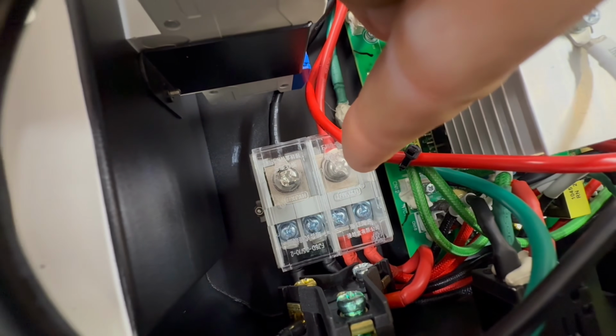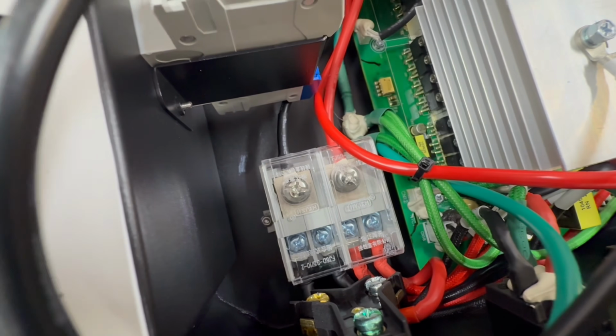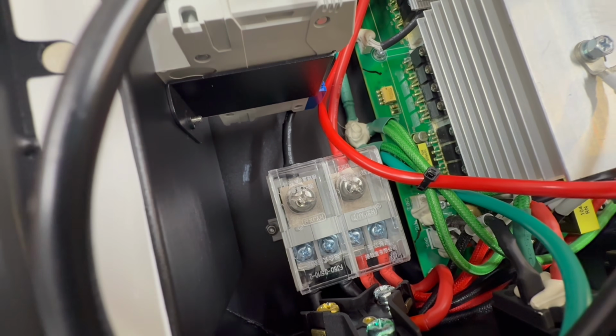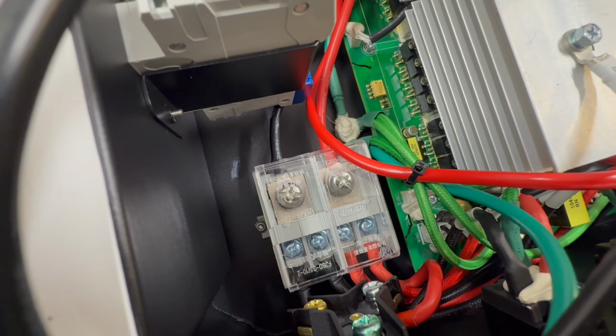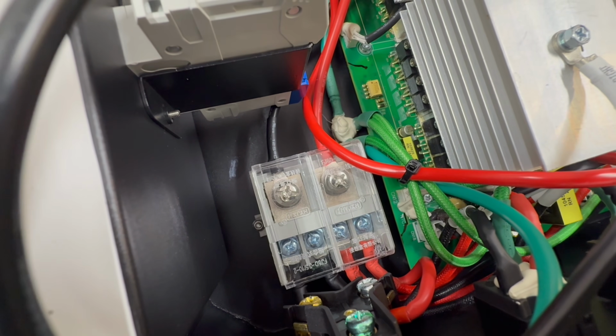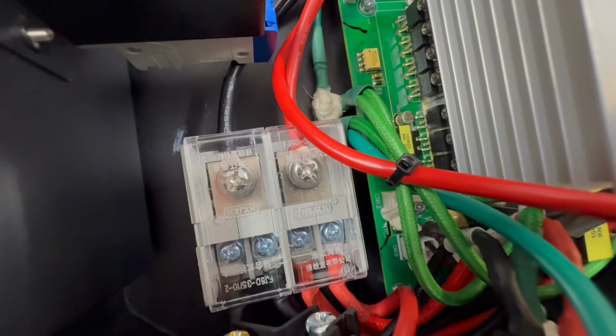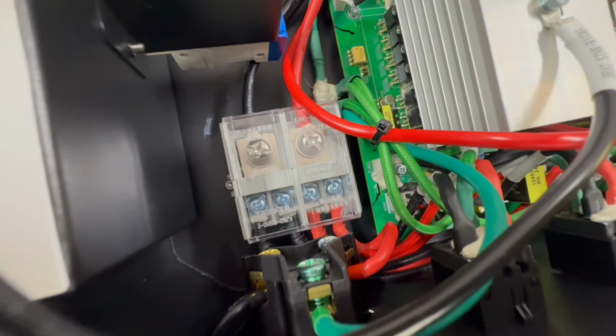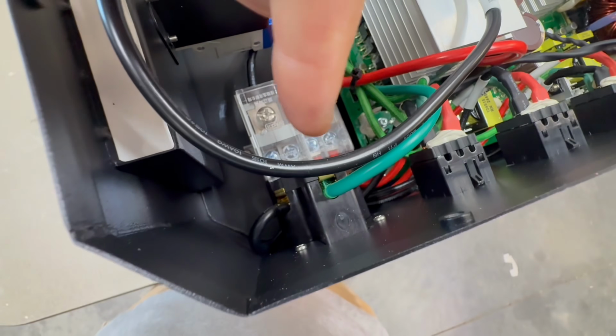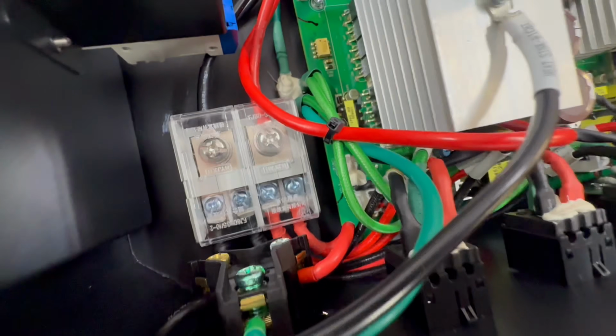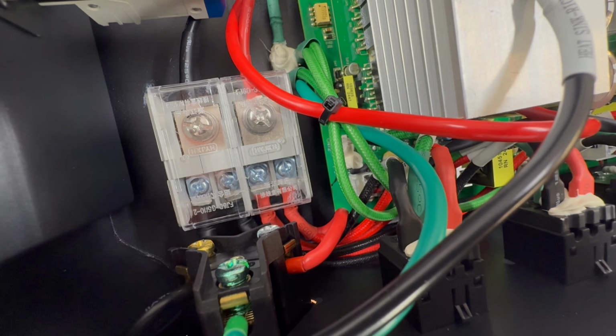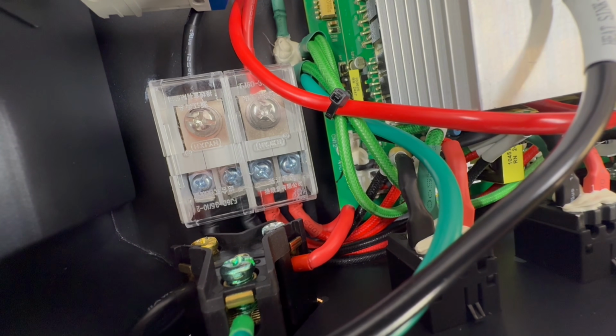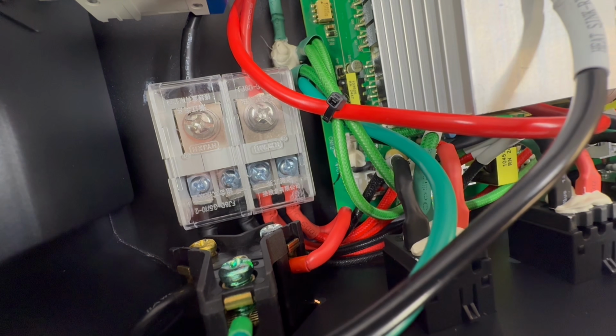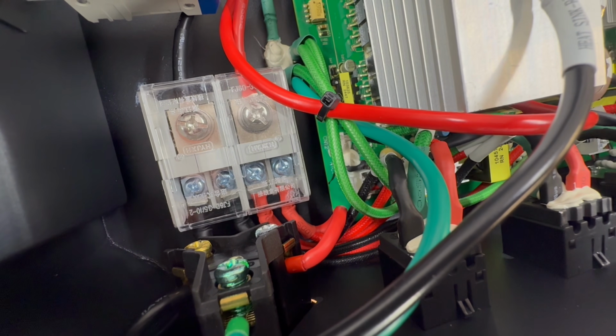This is L1. Over here, though, the black is neutral. So they actually should have had that as a white wire, it's a little less confusing. But the black right there is neutral. And then they've got it split off to each of these outlets, a 30 amp outlet there, 20 amp there. Yeah, you'd have to follow all the black and red instead of black and white.